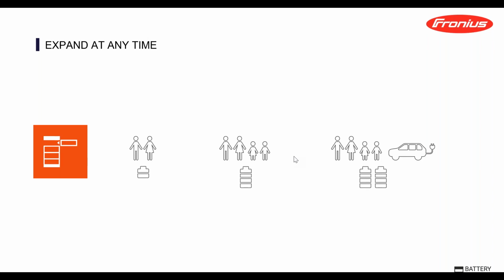Also very important is that it's flexible in time, meaning you can start with a smaller battery and add more later, months or years down the line, without worrying about the system not working or about capacity mismatch. However, this is only truly real in the case of parallel connection. It's still possible to add batteries in series, adding more to a single tower in high voltage, but if the system has run for several years, it may have lost some capacity, so the new battery would need to match the old ones. If you want to maintain full capacity in the new one, connect another tower in parallel.